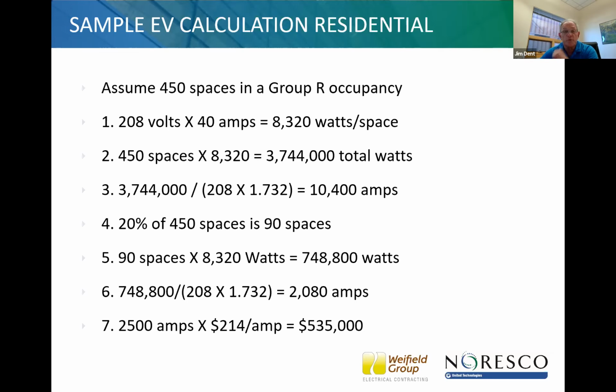So 208 volts times 40 amps is 8,320 watts per space. If you skip down to number 4, 20% of the spaces is 90 spaces. 90 spaces times 8,320 watts is 748,000 watts, divided by 208 times 1.732 is 2,000 amps. So you would have to round that up to a 2,500 amp service, and at $214 an amp, that comes out to $535,000. Next slide, Kevin.